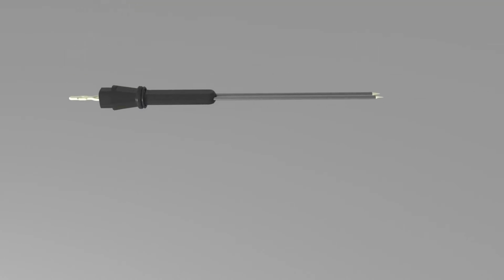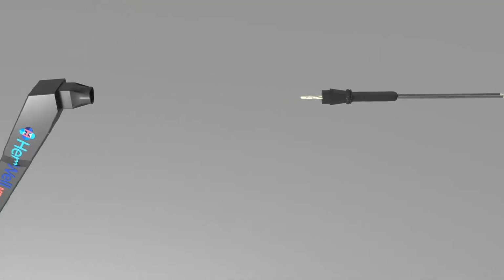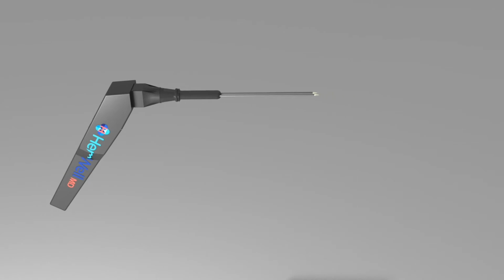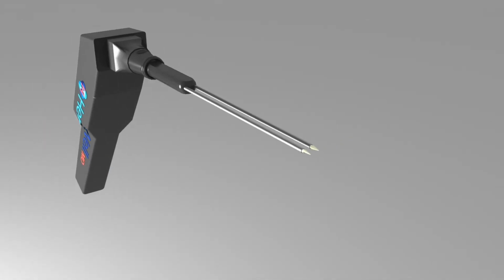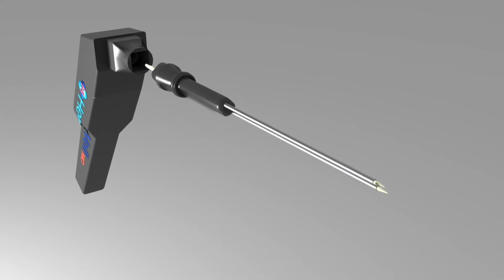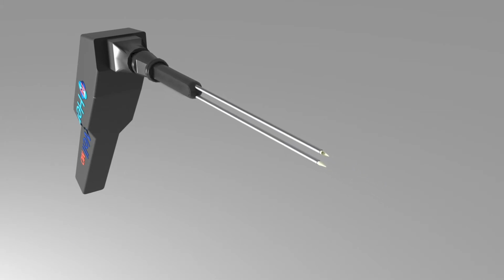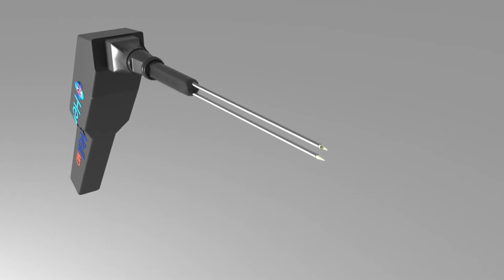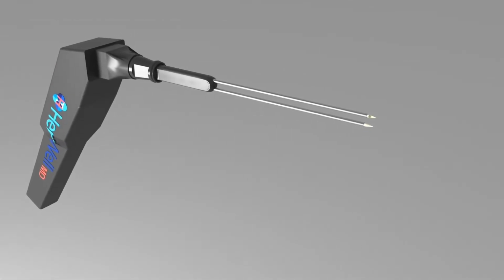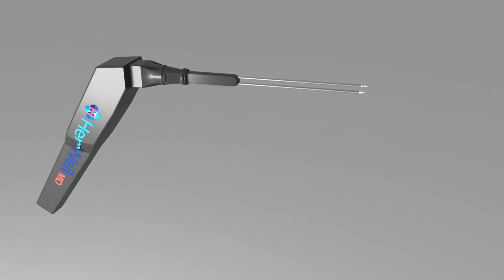Remove the probe from packing. Connect the probe to the handle. To allow both probe tips to make even contact with the hemorrhoid, the probe can be inserted either vertically or horizontally into the handle. This will allow the provider to establish a desired comfort level while holding the handle, depending on the location of the hemorrhoid.